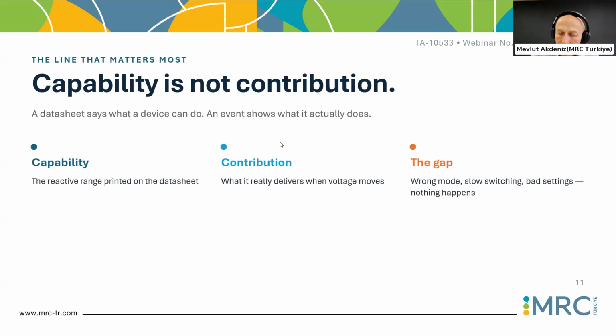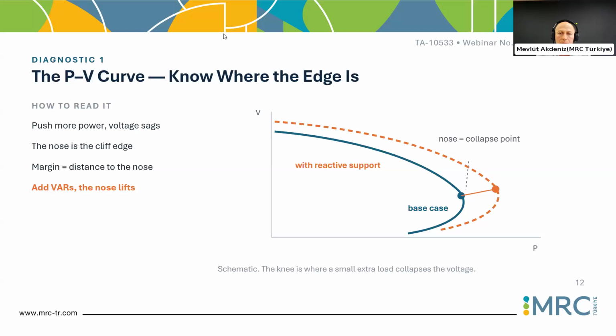So the main gap between the conventional power plants and the IBR type inverter-based power plants, let's call them VRE maybe, is not only the capacity, but the contribution and the settings on the site. So these two points may be more practical topics to be monitored and implemented on site for the TSOs interested in these issues. And once we move to the next page, one of the main issues that can be faced during grid monitoring or grid scanning.